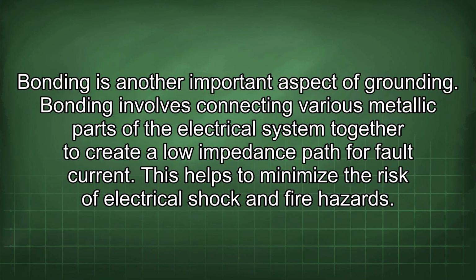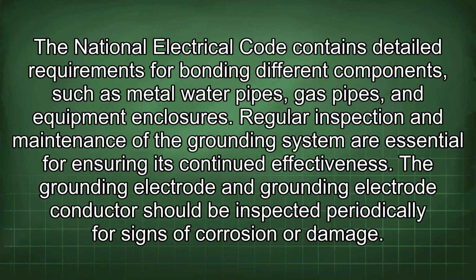Bonding is another important aspect of grounding. Bonding involves connecting various metallic parts of the electrical system together to create a low impedance path for fault current. This helps to minimize the risk of electrical shock and fire hazards. The National Electrical Code contains detailed requirements for bonding different components, such as metal water pipes, gas pipes, and equipment enclosures.